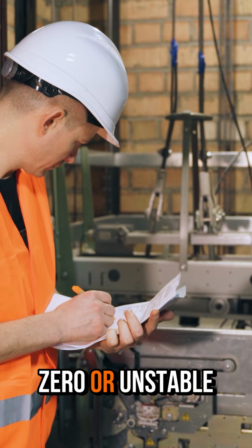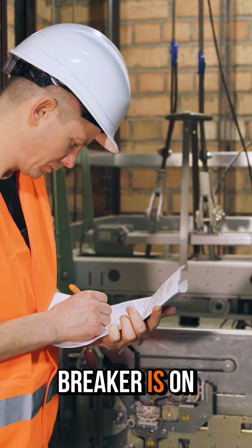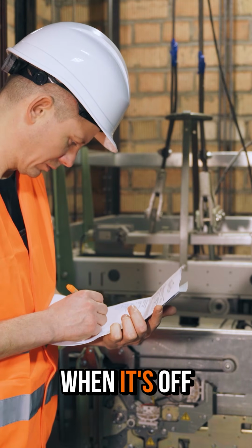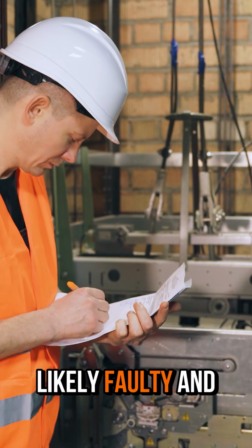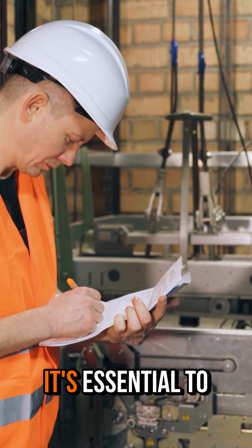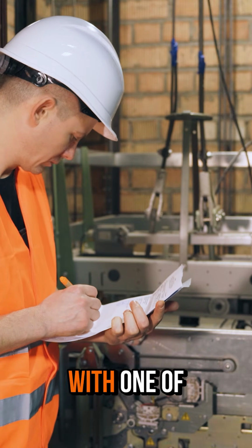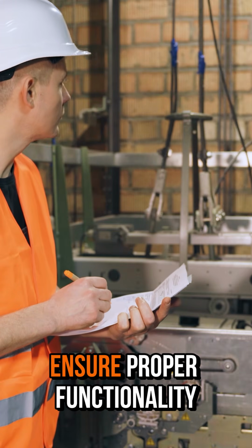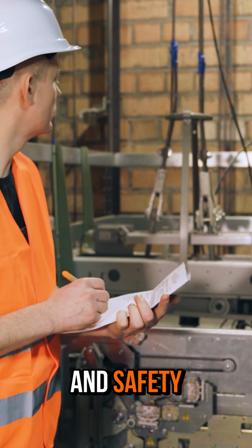If you get zero or unstable voltage when the breaker is on, or no continuity when it's off, the breaker is likely faulty and needs to be replaced. It's essential to replace the breaker with one of the same type and rating to ensure proper functionality and safety.